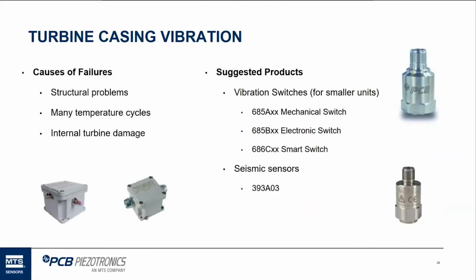And also, we have our, we'll call them seismic sensors, which I've seen these used as well on small units. They provide a low frequency output that would detect casing vibration and provide feedback to maybe a transmitter or other monitoring data acquisition system for providing shutdown or alarms to the operators back at a central control station.